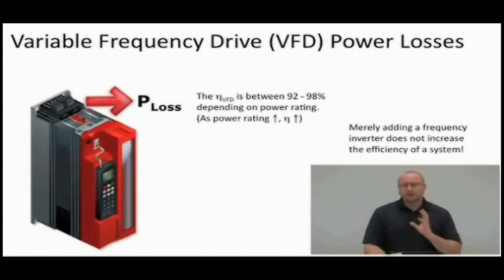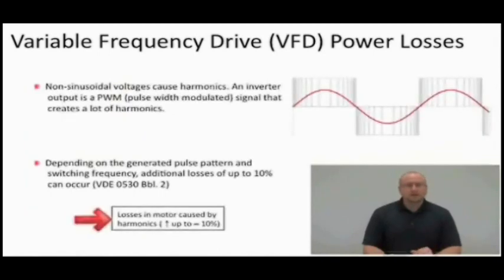But one of the ways that we can really save energy by introducing an inverter is by controlling the speed. Just putting an inverter or a variable frequency drive in your system doesn't introduce efficiency. It actually introduces an inefficiency. Some other losses I talked about: it might make your motor more inefficient, or less efficient, and it does. It's going to create some harmonic losses in your motor.